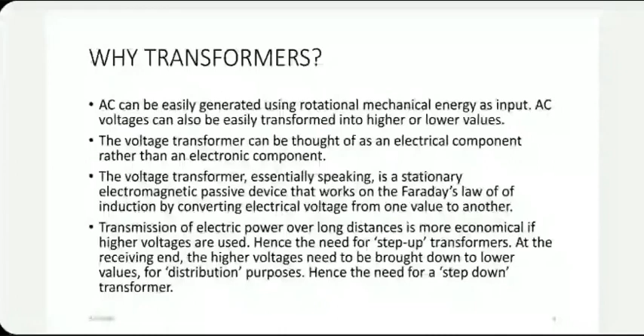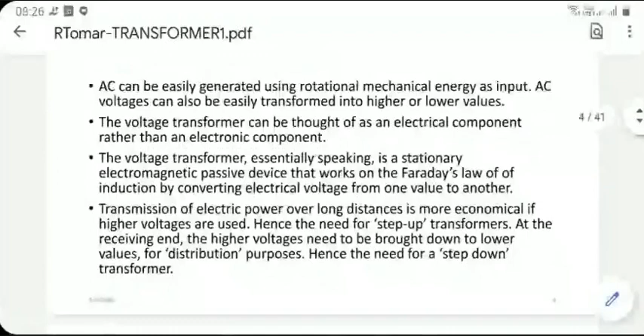Transmission of electric power over long distances is more economical if higher voltages are used. Hence the need for step up, because generation is not at very high voltage. So you need to step up the voltage using transformers before feeding it to the transmission lines. At the receiving end, the opposite has to happen. Very high voltages are coming in. The customer doesn't need that high voltage, so you have to step down the voltage. So a step up transformer on the generator side, a step down transformer on the substation side. By the way, installation of transformers is also a major issue. How it is bolted, where it is bolted, and so on. It is all part of the game.